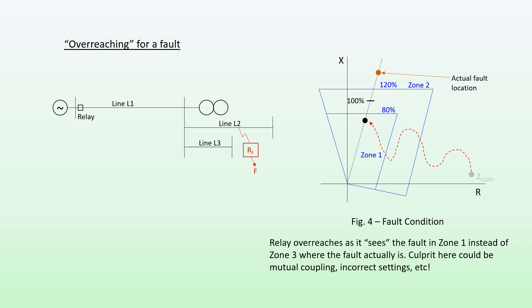So every under-reaching or overreaching operation of the relay does not necessarily lead to an incorrect relay operation from a system point of view. Similarly, if a fault was in Zone 3 but the relay saw it a bit closer — say within the Zone 1 characteristic — then technically the relay has overreached for the fault, but from a system point of view it would have operated correctly.